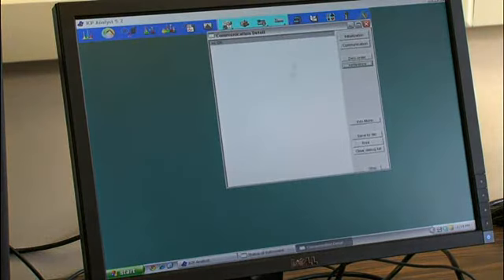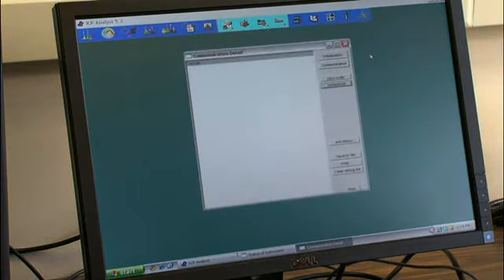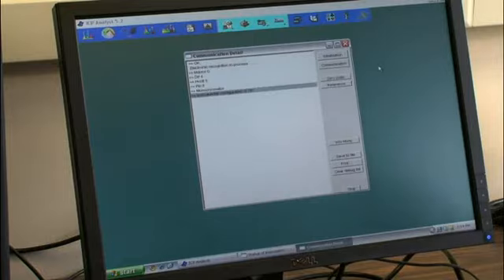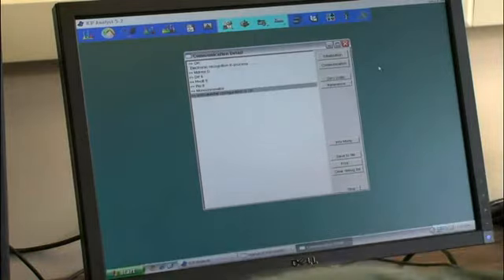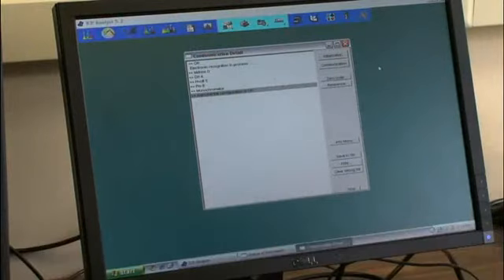So I don't know how much use that is, but okay, here is where we do what's called a zero order and a reference check. And you're going to do this often. The first thing, if for some reason the power's been off, you want to reestablish communication. So you click on that. It'll identify the electronic boards that are in that rack. It'll tell you all the boards and their addresses.